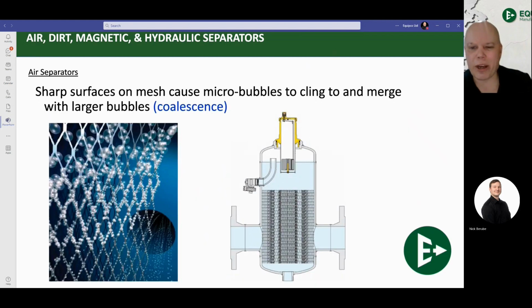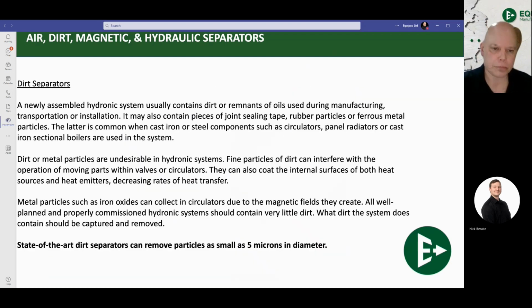This is the little diagram here of what that coalescing media on the inside of an air separator can look like, where it's got all these little pieces on the inside creating all that turbulence, and then the air bubbles are going to stick together. As they get larger and larger, they rise up inside that air separator and eventually burp out of the top. That's your coalescing on the inside.